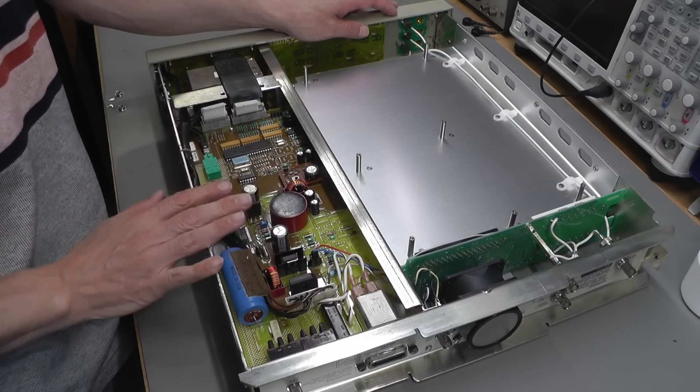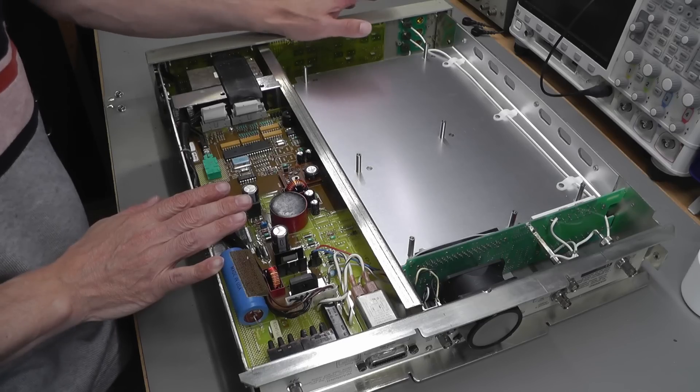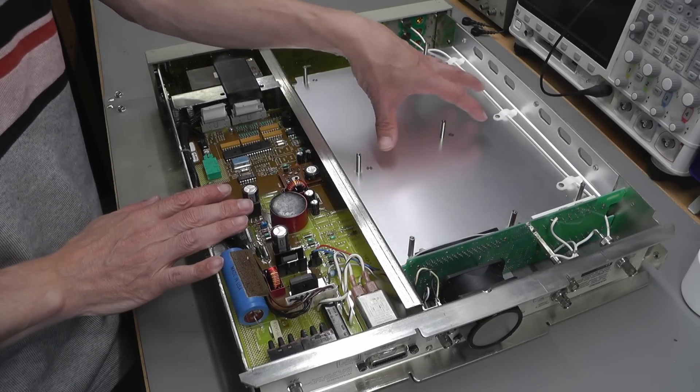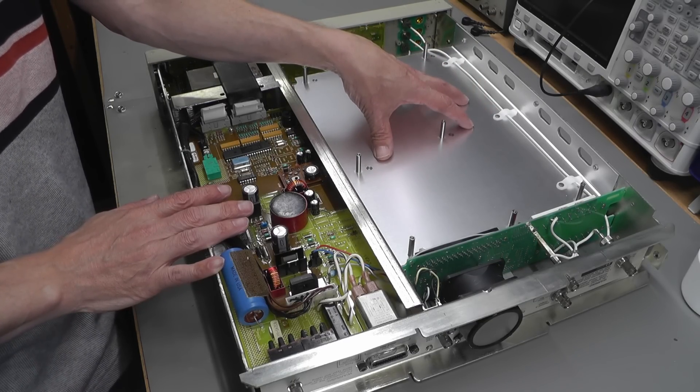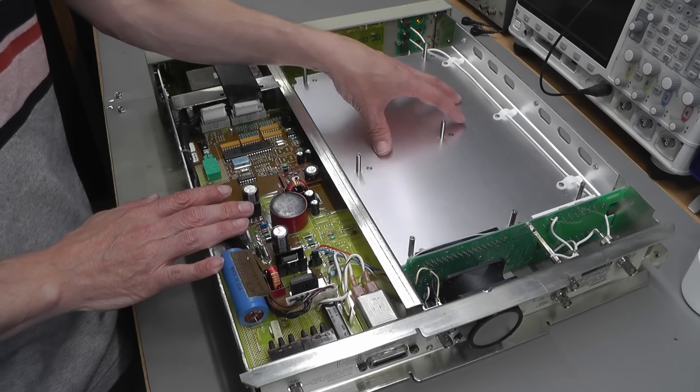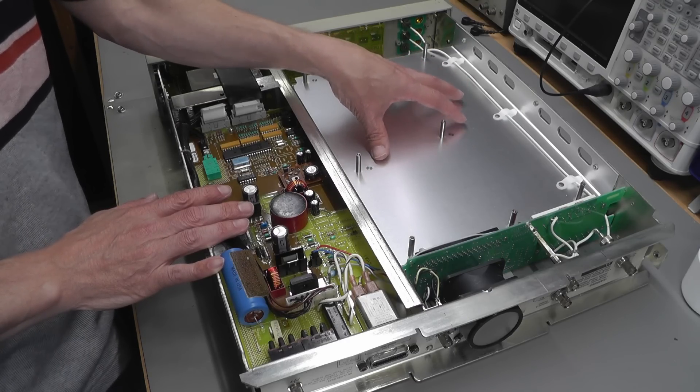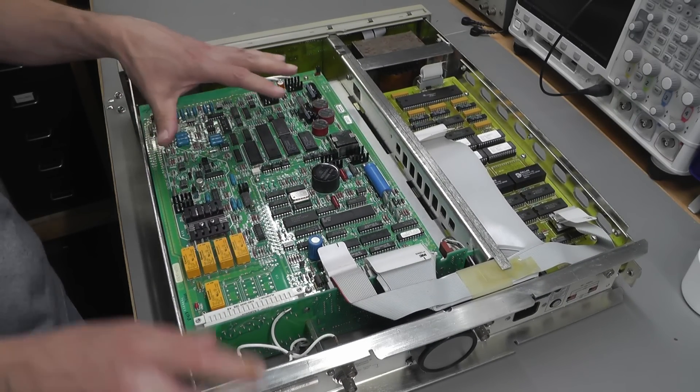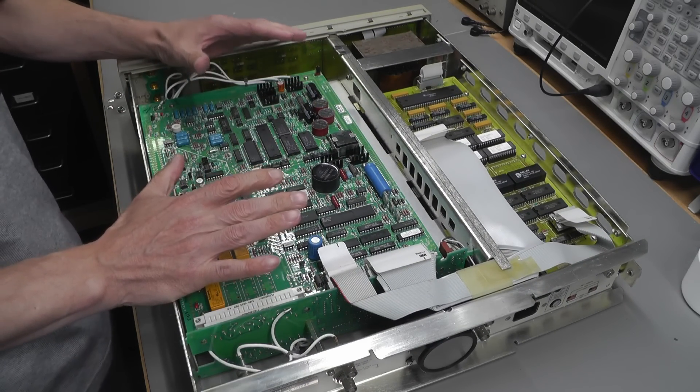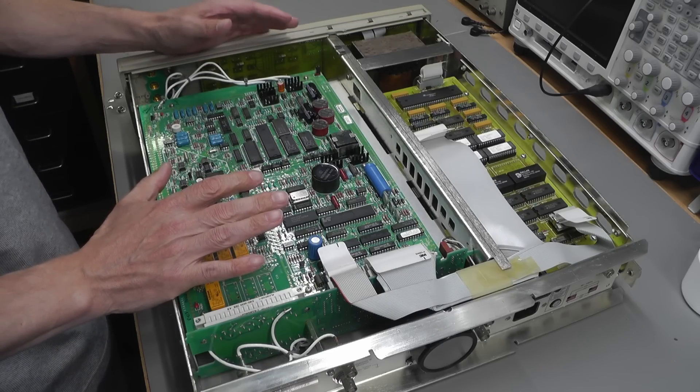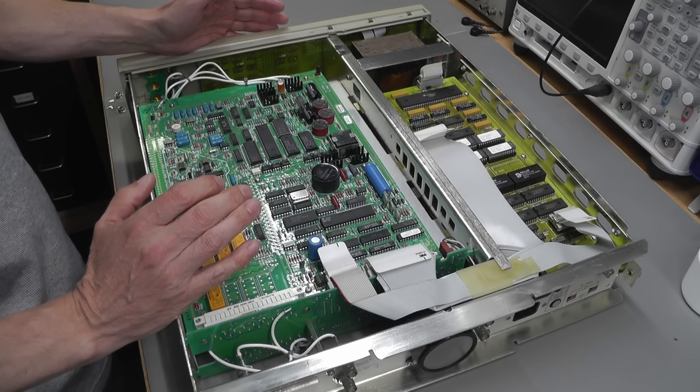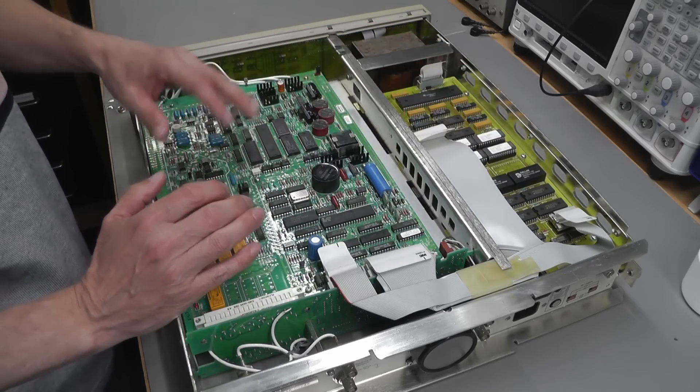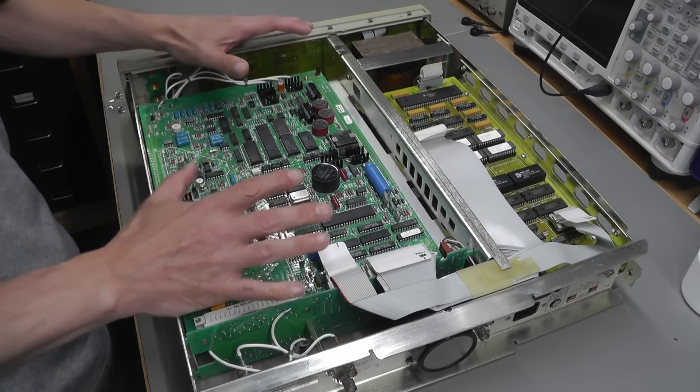This power supply is known as the A6 out guard power supply board. There is an option on this unit that I don't have, which obviously fits in here—the high voltage board, an A3 board, a high voltage amplifier, and it comes under option 002.